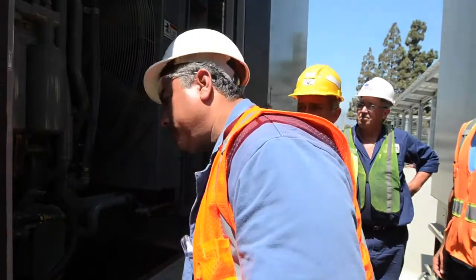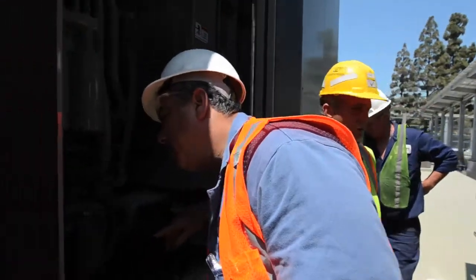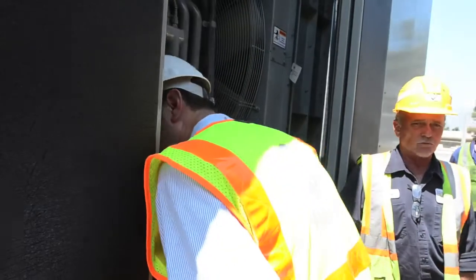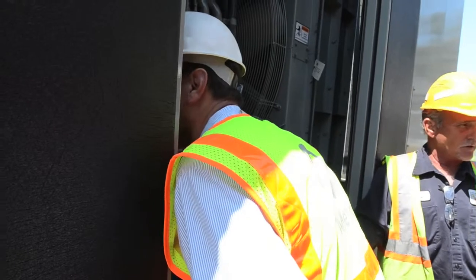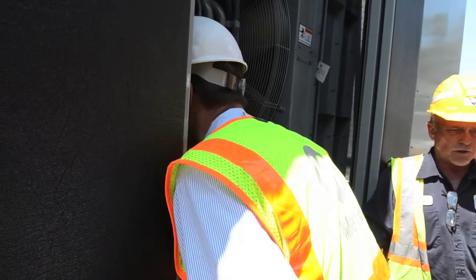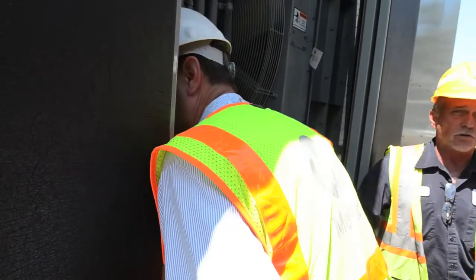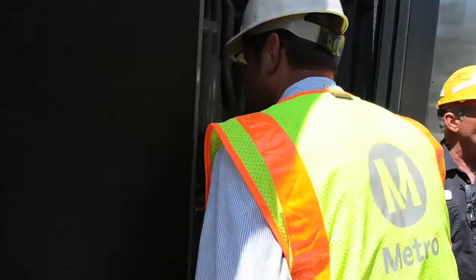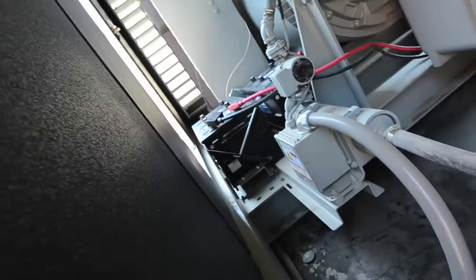If you look down the side right here, where there's no door, that's the jacket water heater. It has a little pump on it, so when it's running, it's always pumping fluid through the system. We come out here four years from now and say you need to change all your hoses and belts, and you say, well, I've only got 10 hours on these things. Take your passenger car, put it in the parking lot, start it up, and let it idle for four years straight—tell me what kind of shape your cooling system's in.